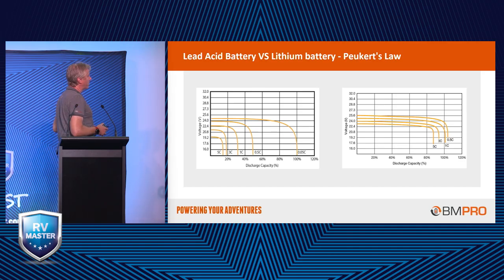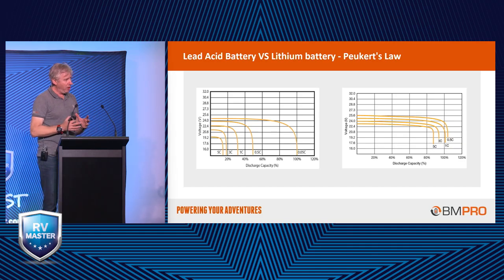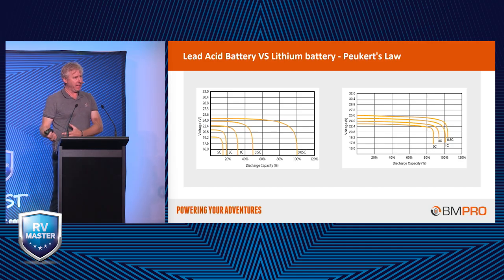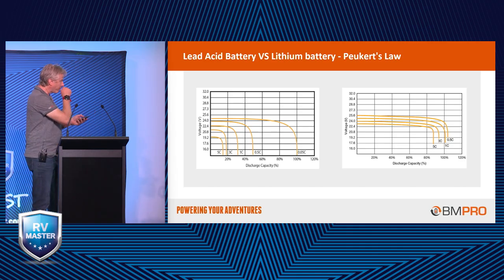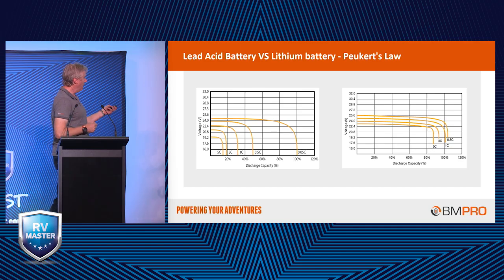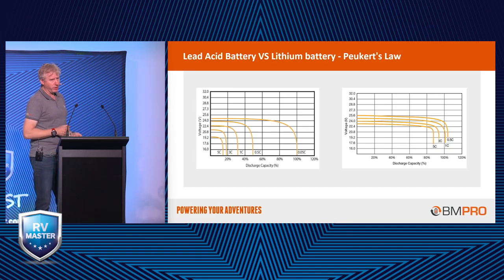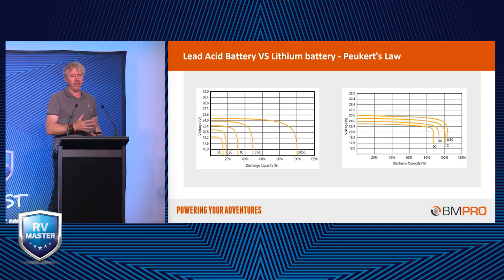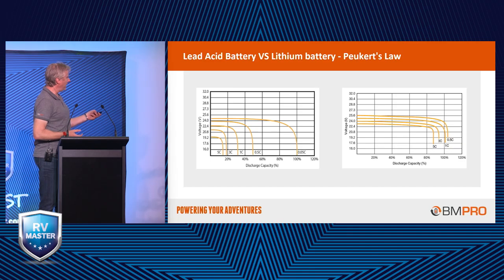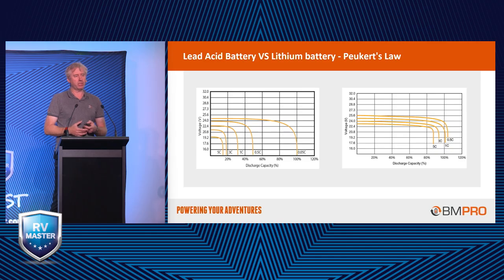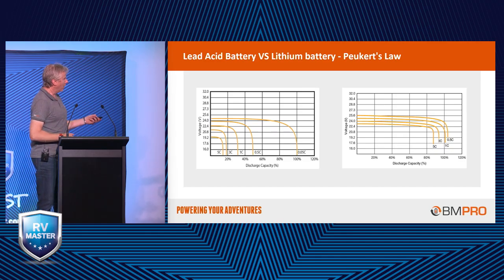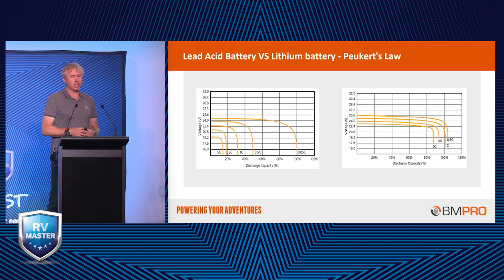This is another one. This is Peukert's law, which from a physics perspective talks about how when you take energy out of a battery faster, you'll have less remaining capacity. So in a lead acid battery, if you take out at 5C, where C is the capacity, say 500 amps in a very short time, well, let's just do 1C. Let's take out the full capacity, because a lot of lithium batteries advertise that you can take 100 amps out very quickly and still use that available capacity. When you take out 1C on a lead acid battery, it's only going to last approximately 30% of its capacity, whereas these lithium batteries are designed to be thumped in, thumped out, and you're still going to get pretty much that full capacity, in the high 90s. So even if you discharge it at full capacity, at 100 amps at a time, you're still going to get the full capacity out of it.